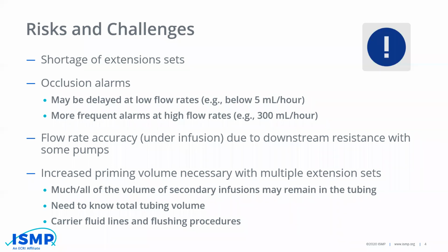Also, another thing that happened with the extension sets: the occlusion alarms. You're going at a very low flow rate, and it might be delayed by the time the solution actually got to the point that it would cause an occlusion alarm. So those rates were very, very low, as you can see on the slide. And then more frequent alarms if the fluid was running at very large amounts per hour, like 300 milliliters and above. So that was an issue as well.